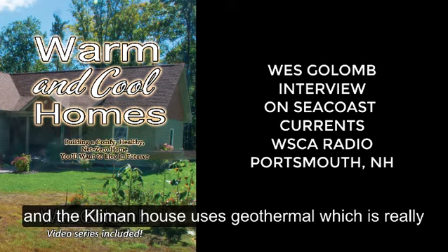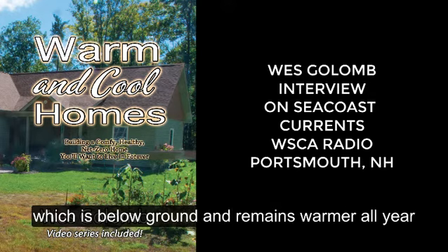And typically, in most cases, you put 1 unit of electricity, in this case generated by solar, and you get about 3 units out of heat energy. So this is a very efficient way of leveraging electric energy to heat. Several of the houses just use this system, the heat pump, and the Kliman house uses geothermal, which is really a heat pump, but they're getting the heat from water, which is below ground and remains warmer all year.